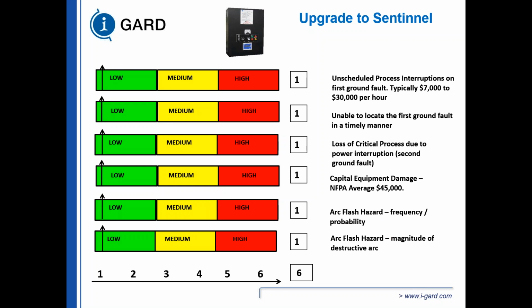And the arc flash magnitude now is low because we trip when we have an arc flash, so we're able to lower the incident energy, because incident energy is directly proportional to time. The faster we clear that fault, the lower the incident energy. So with the smart HRG system, your risk meter goes down to 6.